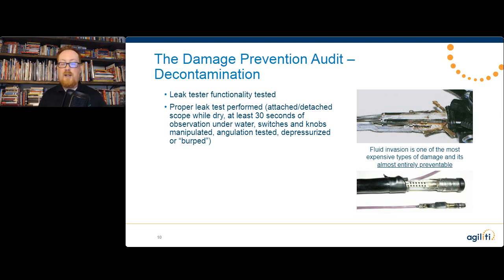This becomes a very significant issue if you're using probably the most common leak tester on the market, which is the continuous airflow leak tester, where you plug it in and it just kind of pushes air through, and it's up to you to visually identify when a leak is happening when you do the leak test. Now, if that leak tester is not pushing air through, guess what you're not going to find? Leaks.